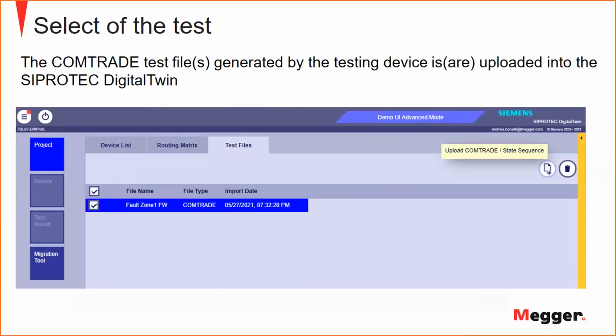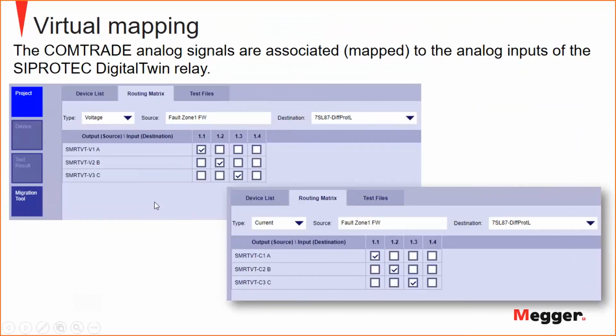The COMTRADE files that I've generated with my test set are uploaded into the Siprotec digital twin. So this is my COMTRADE file. The analog signals that you can find in the COMTRADE files are mapped to the analog inputs of the digital twin relay. They use the voltages A, B, C, and currents A, B, C. And I connect to current transformer 1, current transformer 2, current transformer 3, voltage transformer 1, voltage transformer 2, voltage transformer 3 of the protection relay digital twin.